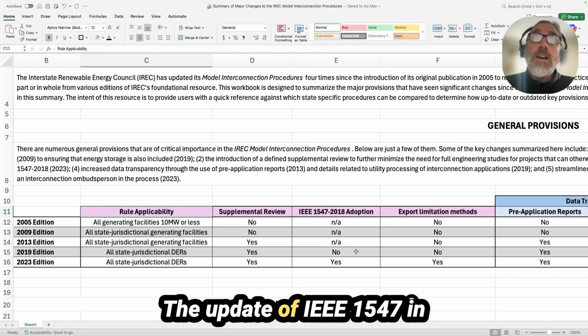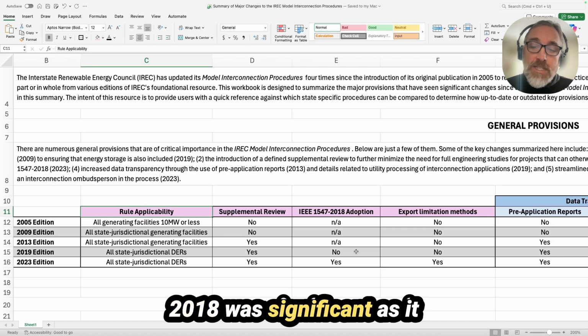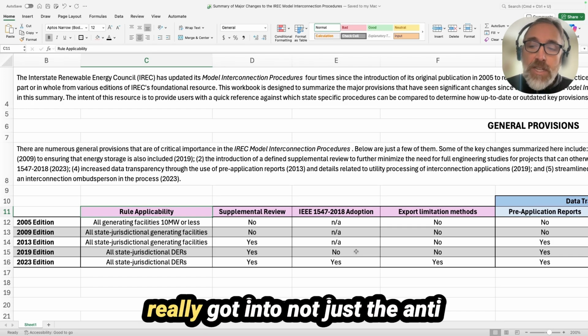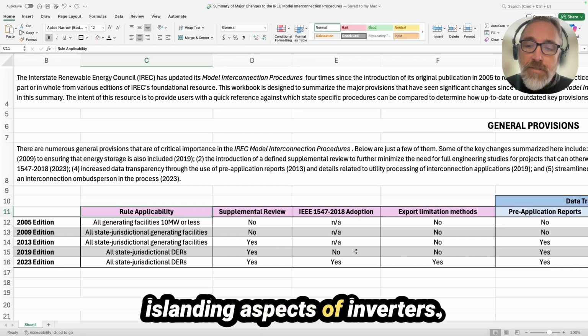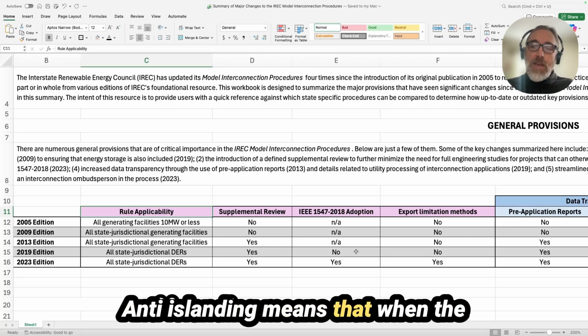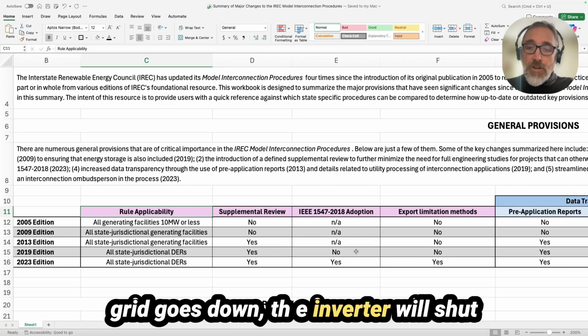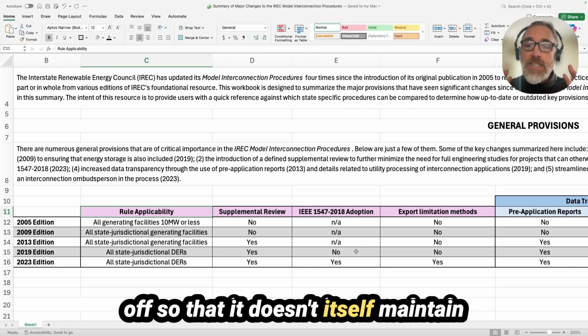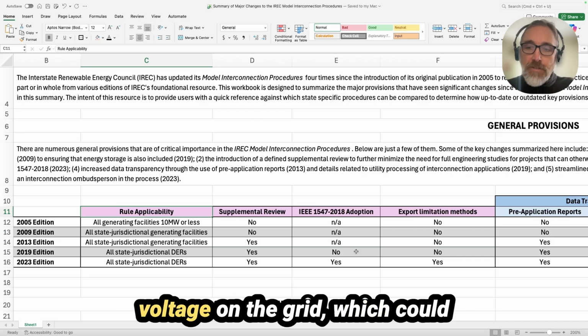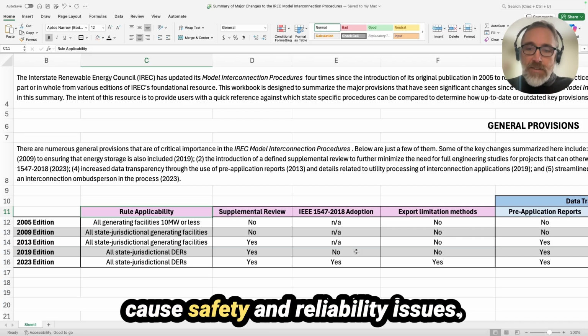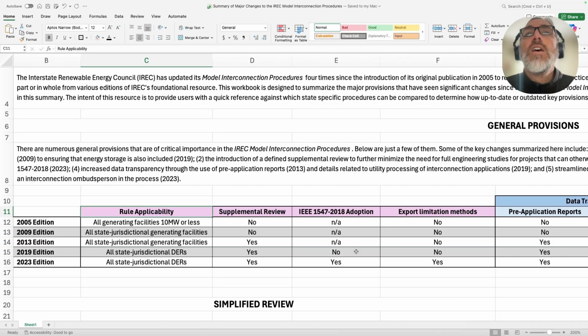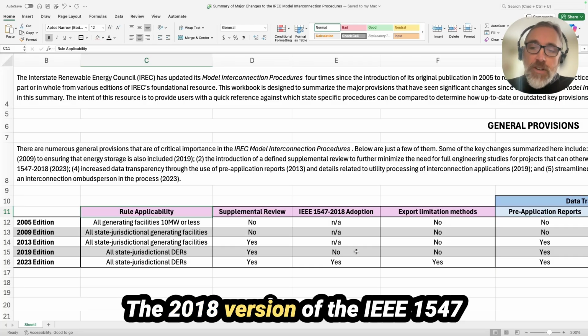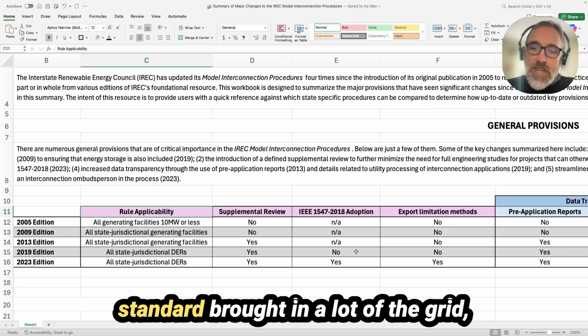The update of IEEE 1547 in 2018 was significant, as it really got into not just the anti-islanding aspects of inverters. Anti-islanding means that when the grid goes down, the inverter will shut off so that it doesn't itself maintain voltage on the grid, which could cause safety and reliability issues.